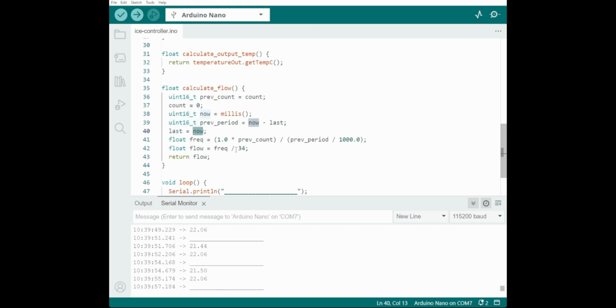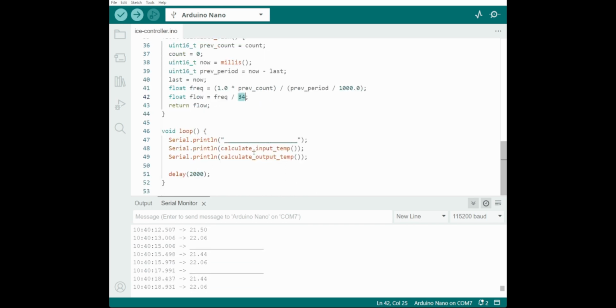And then you run through this math. Now that 34, we'll have to check by measuring how much water's flowing in the system when I turn it on. But hopefully that should be vaguely right, because I've got exactly the same sensor on the output, and the icing and the cooling system has the same model of sensor bought at roughly the same time, so they should be roughly calibrated.